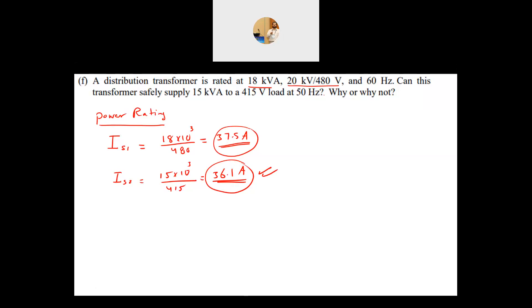The second point is about the change from 60 to 50 Hz. I've prepared a separate video on whether you can use a transformer from 60 to 50 Hz or vice versa — I'll leave a link for it. This question is more tricky because I'm changing both the frequency and the voltage rating. The fundamental formula for transformer design is: voltage per turn = 4.44 × F × B × A, where A is the cross-sectional area of the core.